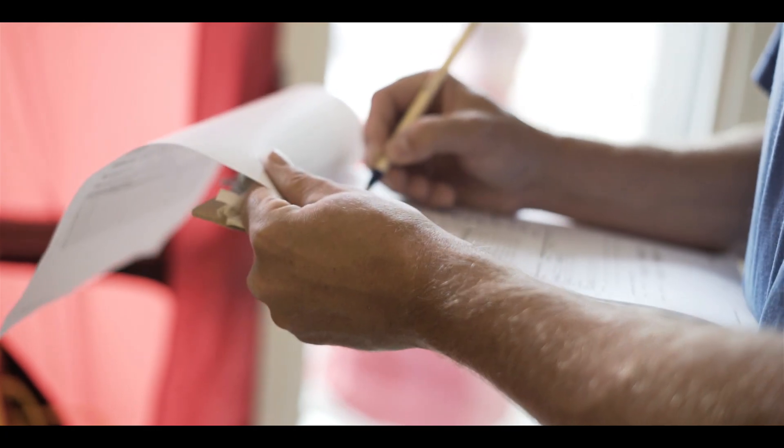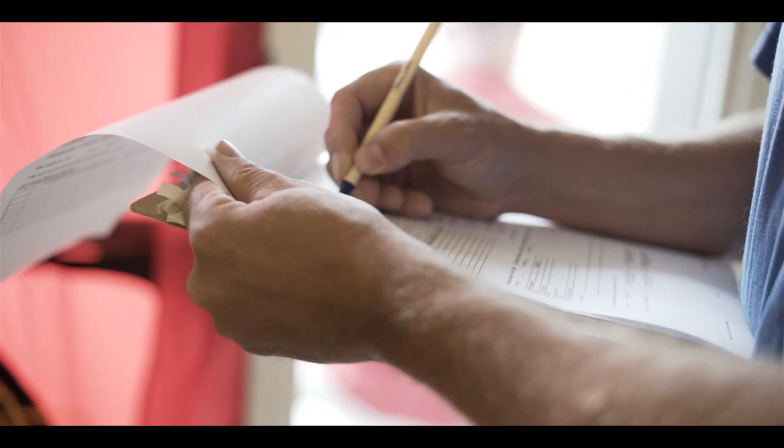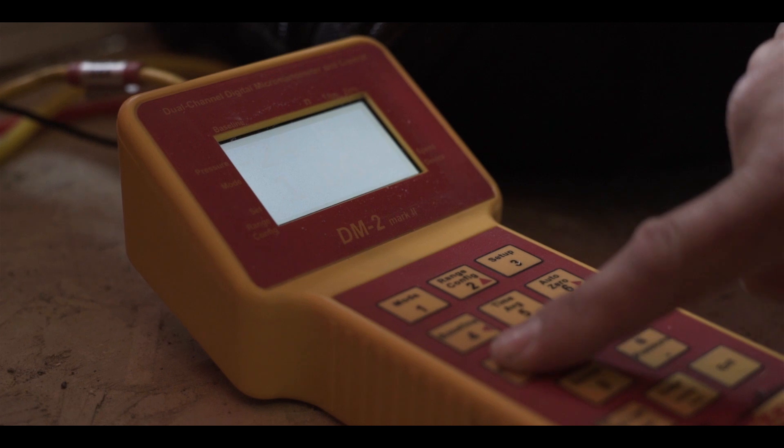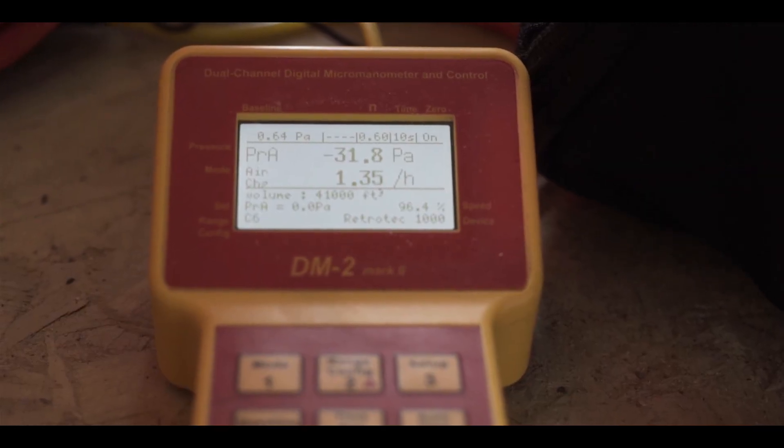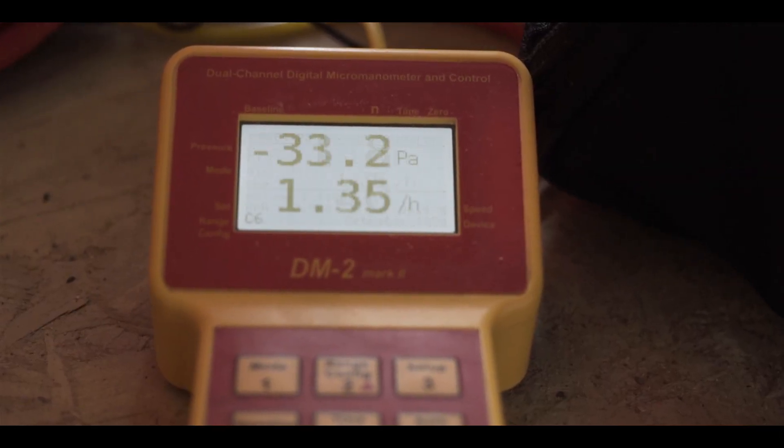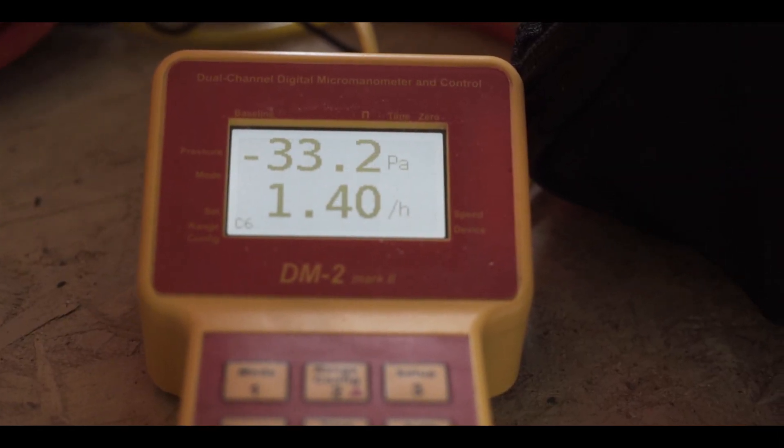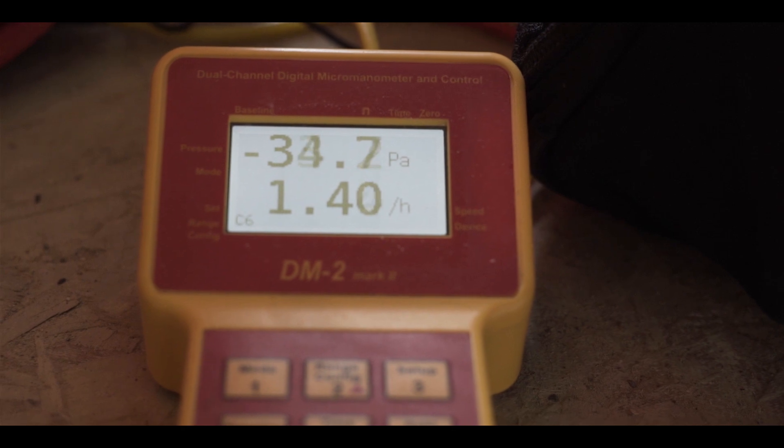The main metric we use for air tightness is air changes per hour at 50 pascals. The target that I have is 1.5 air changes per hour at 50 pascals.